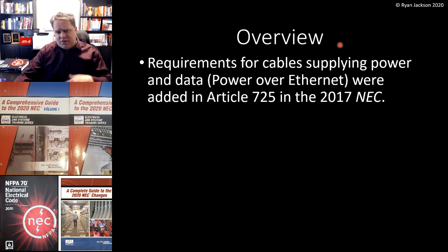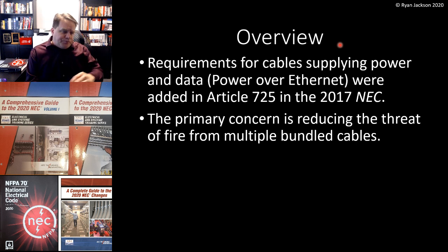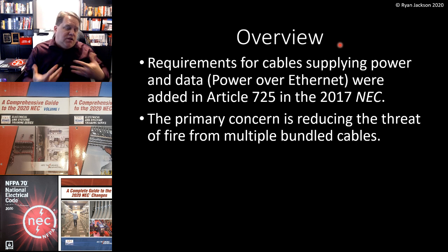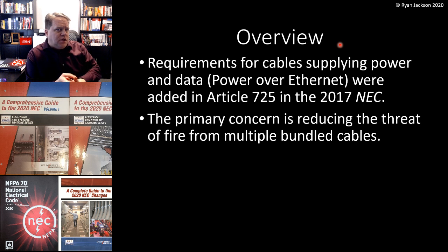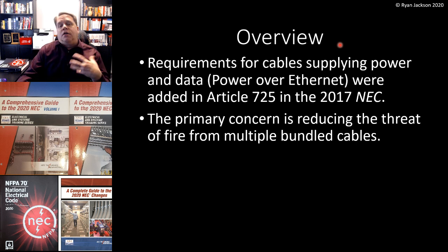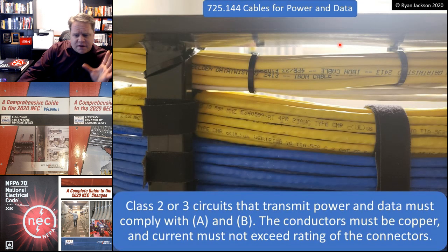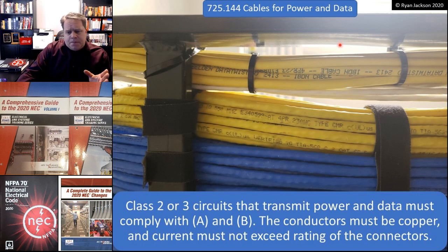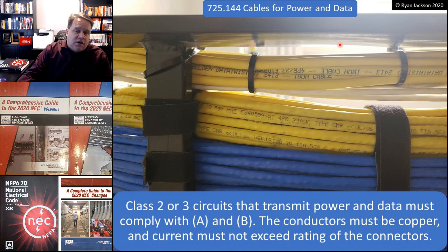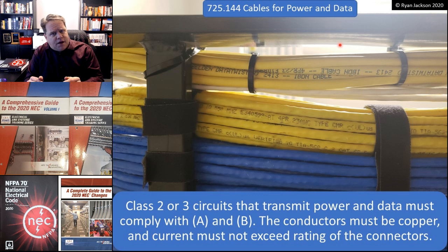We added these rules in the 2017 NEC because of power over Ethernet, and mainly power over Ethernet lighting, which is becoming fairly popular. The primary concern for why we had to add this in the NEC is that it's low voltage and low current. If it's limited in power, voltage, and current, why are we so concerned? The main issue is reducing the threat of fire that can arise from multiple bundled cables. Section 725.144 is where we begin — cables for power and data. Class 2 or class 3 circuits that transmit both power and data must comply with A and B. The conductors have to be copper, and the current must not exceed the rating of the connectors.